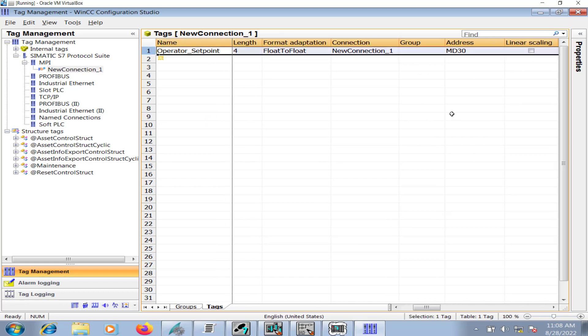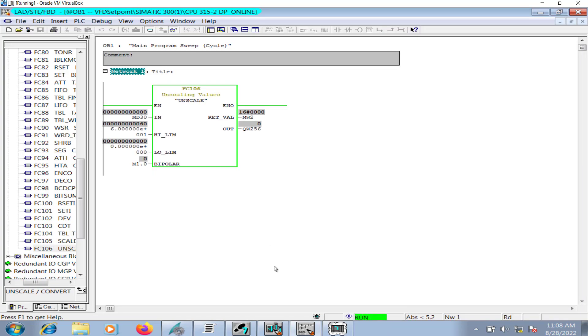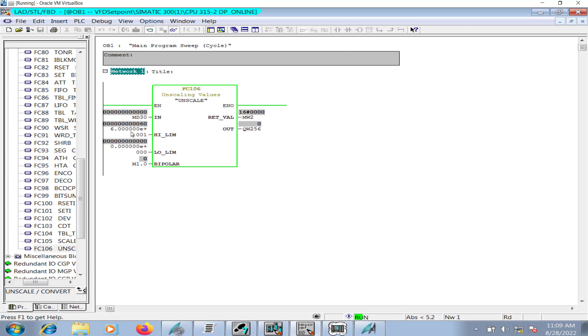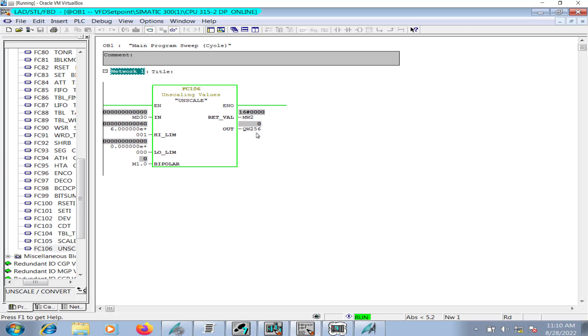Now the connection setting and the entry of the required variable MD 30 is successfully made. If the connection between the PLC and HMI is established, then this value MD 30 would be unscaled between 0 to 60 Hertz and would ultimately be converted to the hex value. Then 4-20 milliampere would emerge out of the analog output channel of the PLC. Those 4-20 milliampere would be fed into the VFD analog input channel for operator set point, and so the induction motor will change its revolutions per minute according to the frequency of the VFD.